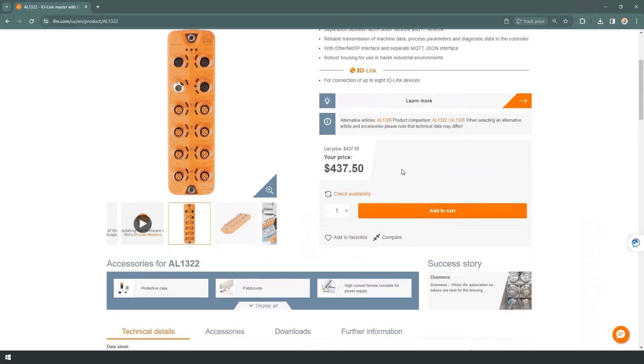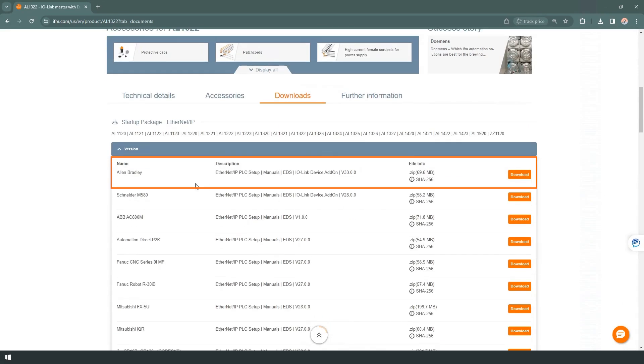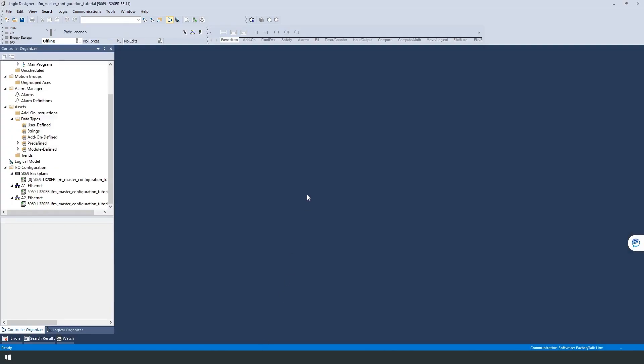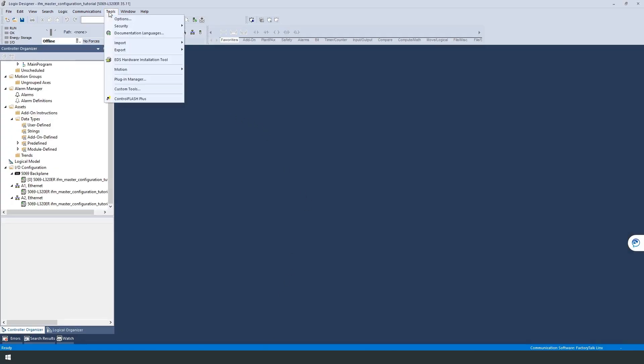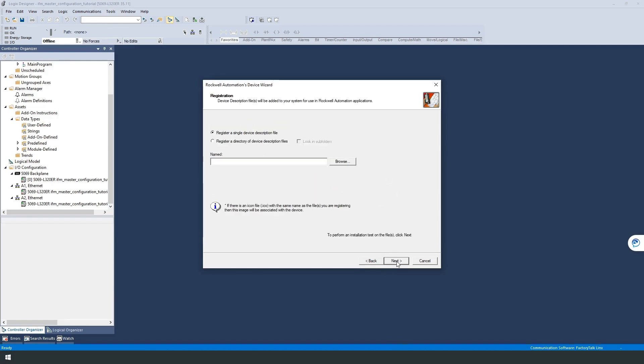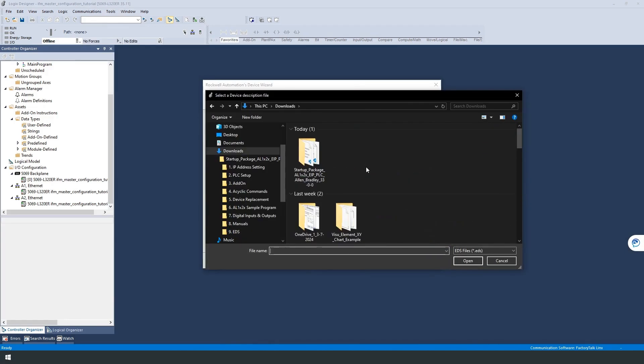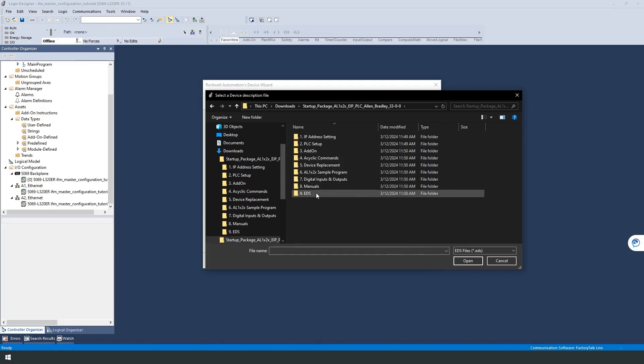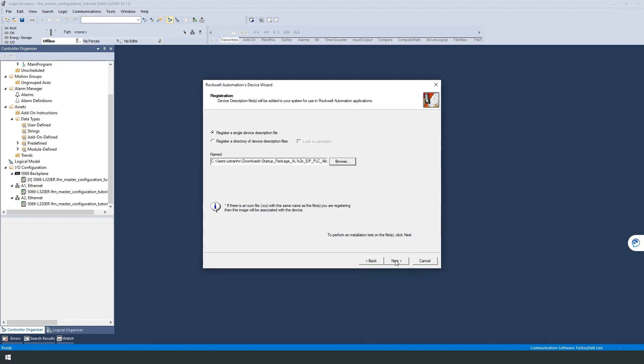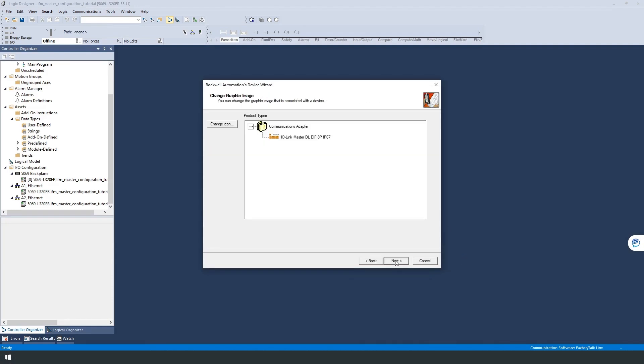In order to configure the IO-Link master in Studio 5000, we have to install its EDS file first. This file and other useful tools can be found in the starter package of the IO-Link master. We select the Allen-Bradley package. We have already downloaded the package and are now ready to install the required file. In the Studio 5000 software, you will find the EDS hardware installation tool under the Tools tab at the top. Follow the wizard and select the file for the IO-Link master used from the EDS folder in the starter package. Once the file is installed, we can implement it in our software.